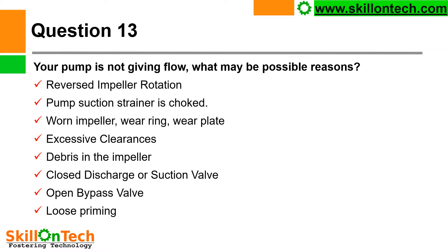Open bypass valve: if the bypass valve is open, flow will come back to the suction through the bypass line and you will not get sufficient flow in the discharge pipeline. Loss of priming: if your pump is losing priming again and again, air inside the casing or suction line is being compressed repeatedly and the pump will not give you the appropriate flow it was designed for.